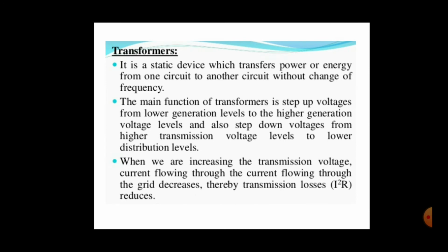Next, we will see transformers. It is a static device which transfers power or energy from one circuit to another circuit without change of frequency. The main function of transformers is to step up voltages from lower generation levels to higher transmission levels, and also step down voltages from higher transmission voltage levels to lower distribution levels. When we increase the transmission voltage, the current flowing through the circuit or grid decreases. Thereby, transmission losses, I square R losses, are reduced.